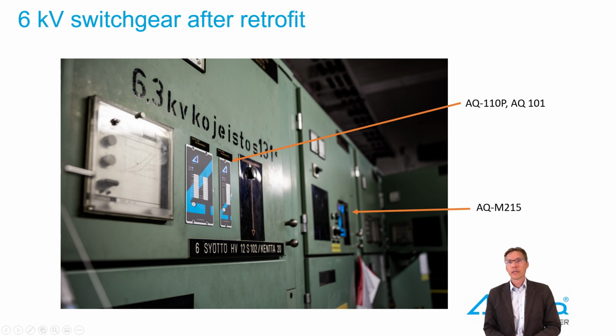All right, we've seen how the quenching device operates. Here, actual pictures of the 6 kV switchgear after the retrofit activity. So the original switchgear is from the 1970s. You can see door-mounted AQ100 series devices, AQ110P, AQ101, and then down on the line you see AQ-M215 and motor protection IED installed.